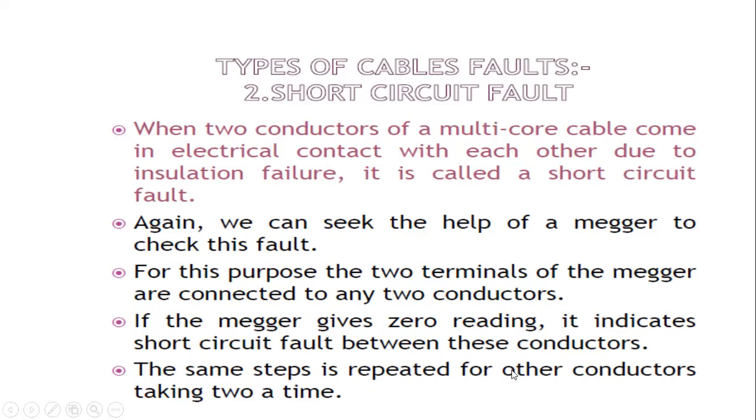The same step is repeated for the other conductors, two at a time. If the Megger does not measure the zero value, then there is no short circuit fault.